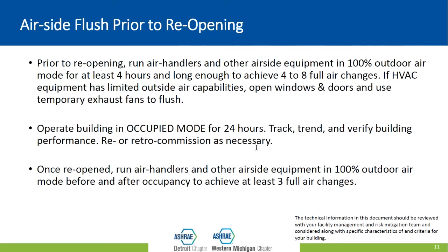Next slide. Before you welcome your occupants back into your building, you want to make sure that you've done an airside flush. The building has been dormant for several weeks, and now it's full of old, stale, stagnant air. You want to get that air out of there. To do that, if possible, depending on the capabilities of your equipment, you want to operate the system at 100% outside air mode, or at least long enough to achieve 4 to 8 or more complete air changes. That means you want to have taken all the air currently in the building, gotten rid of it, and brought in new air at least 4 to 8 times. If you can't do that with your existing equipment, then you may also want to consider opening windows and doors or using temporary exhaust fans.